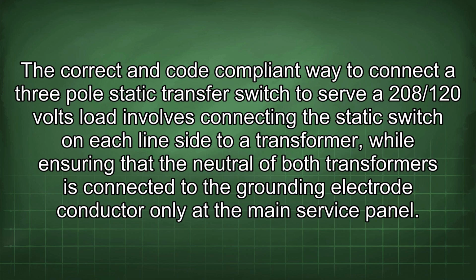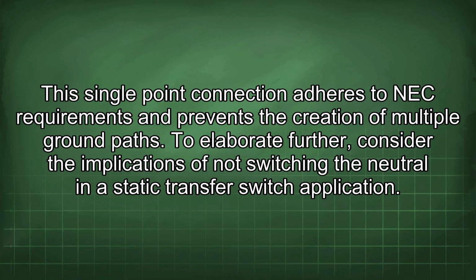The correct and code-compliant way to connect a 3-pole static transfer switch to serve a 208/120 volts load involves connecting the static switch on each line side to a transformer, while ensuring that the neutral of both transformers is connected to the grounding electrode conductor only at the main service panel. This single-point connection adheres to NEC requirements and prevents the creation of multiple ground paths.